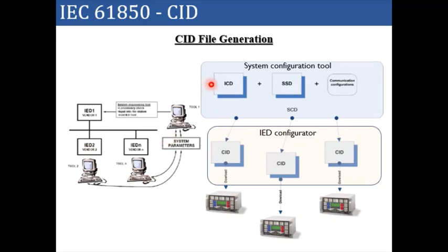Those ICD files will be imported in the system configuration tool, and then along with the SSD file and the communication configuration details, the SCD file is generated. So the SCD file is nothing but the substation configuration description. Specific to a substation, this configuration tool will create the SCD file to describe the substation activities.